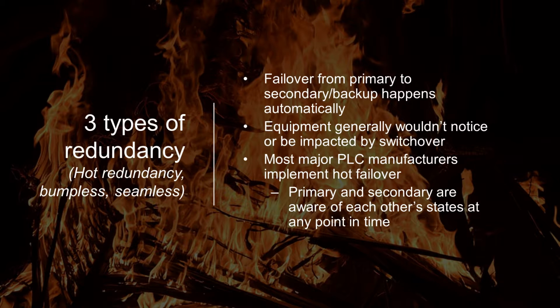The third type of redundancy, which is the primary subject for today's webinar, is what we refer to as hot redundancy. In this type, everything is automatic, meaning you'll typically have controllers or automation in place such that if the primary controller or control mechanism fails, the secondary control mechanism will take over, and it will be seamless or not noticed by the equipment or process.